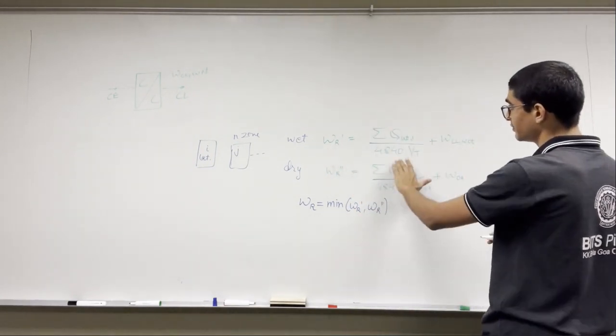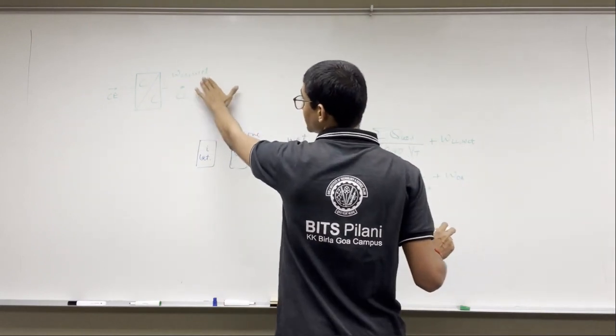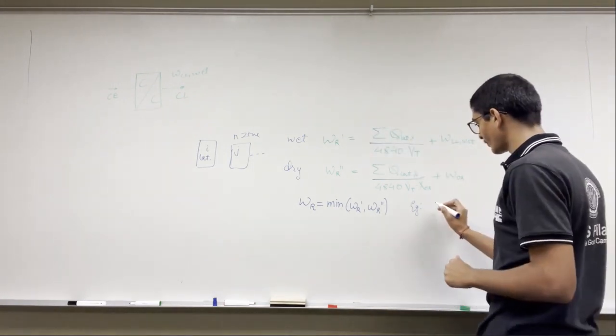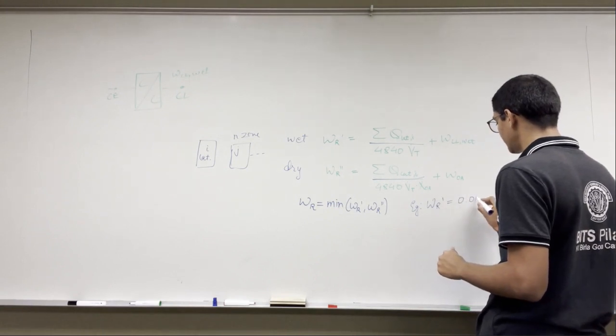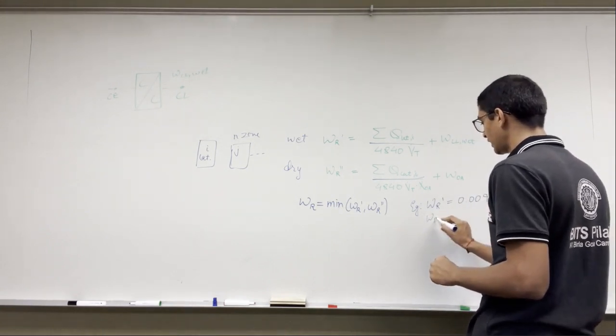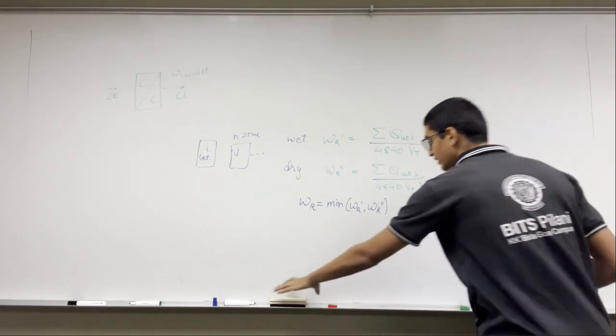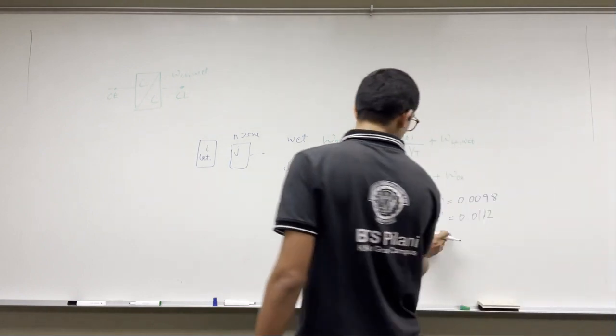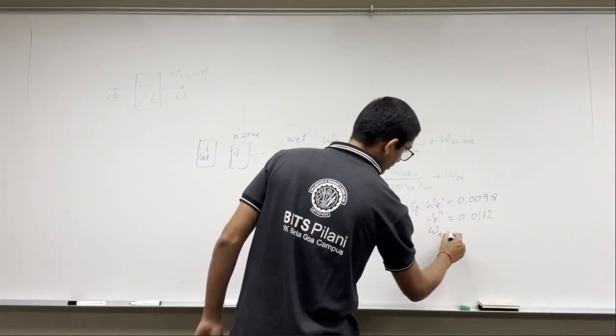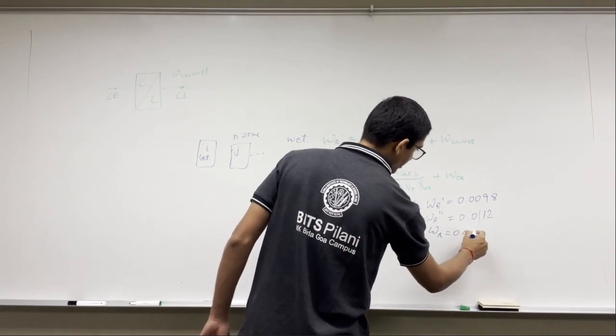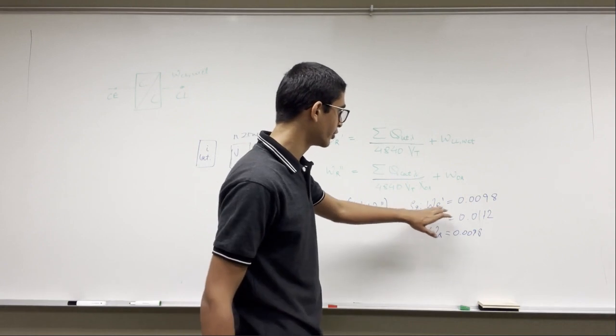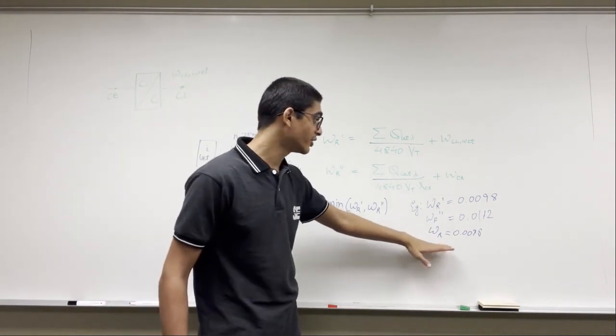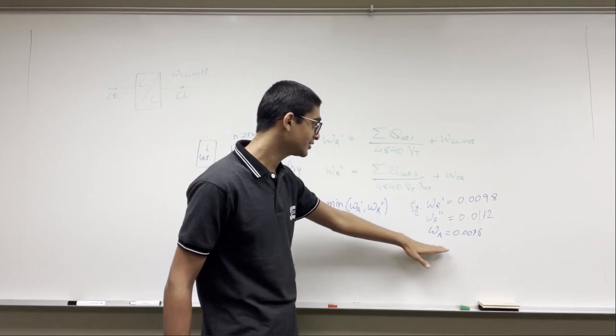Omega_r, which is the minimum of the two, is 0.0098. That means the minimum condition is coming from omega_r prime. Omega_r prime represents a wet coil condition, which indirectly means that in this specific case we have a wet coil. That's the way we find out the value of omega_r.